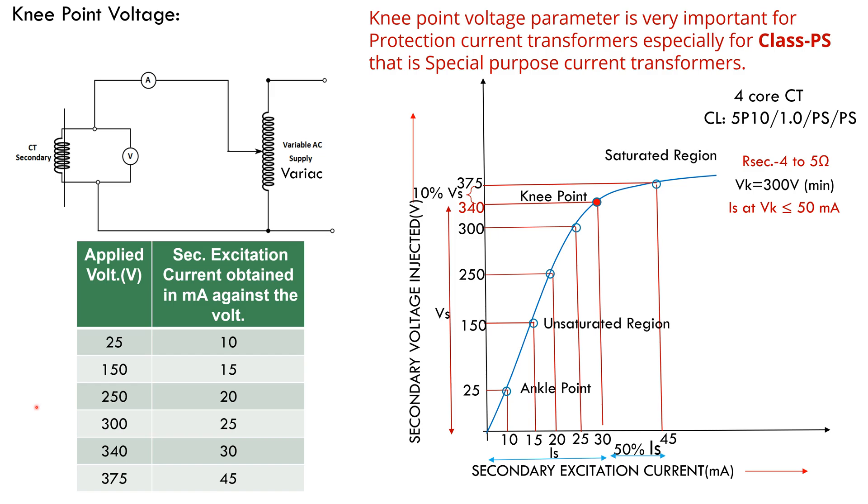If we recall the definition of knee point voltage, the value of voltage at which when the voltage applied is increased by 10% causes the exciting current to increase by 50%. At 375 volt applied voltage, the current rises abruptly to the value of 45 milliampere.